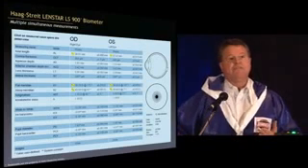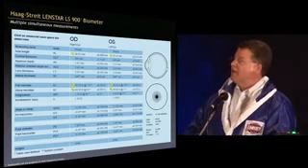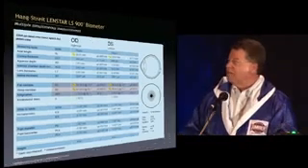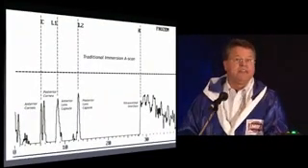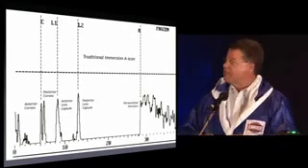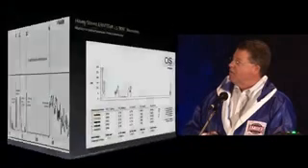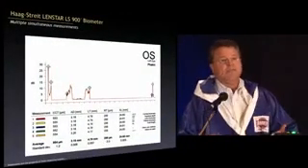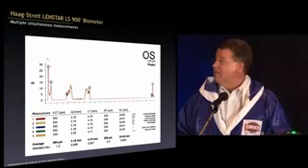You get a tremendous amount of information — this is with one button push for each eye. This is what you get, and these are just the Ks right here. So we all know what this is — this is an immersion A-scan: anterior cornea, posterior cornea, anterior lens capsule, posterior lens capsule, vitreo-retinal interface. With the LENSTAR, it gives you that information looking just like an immersion A-scan.